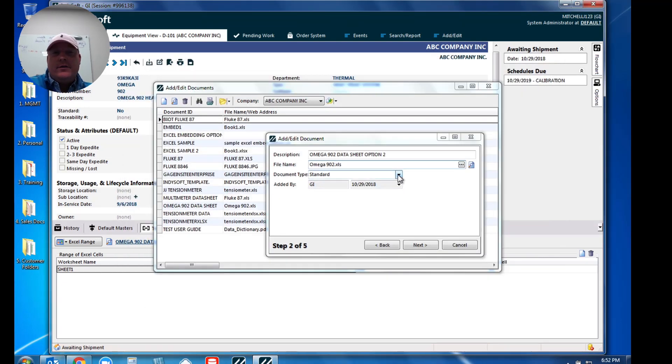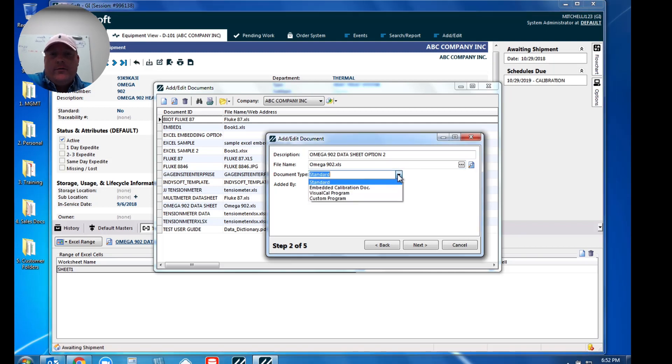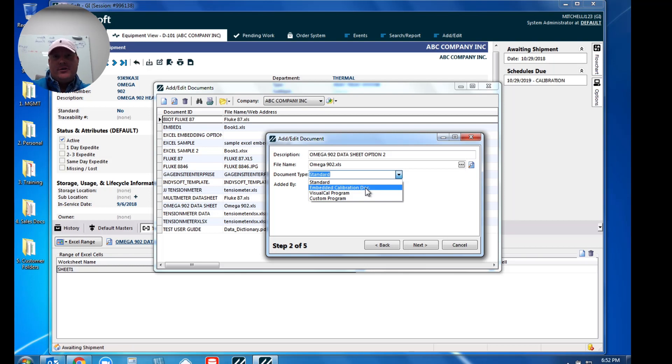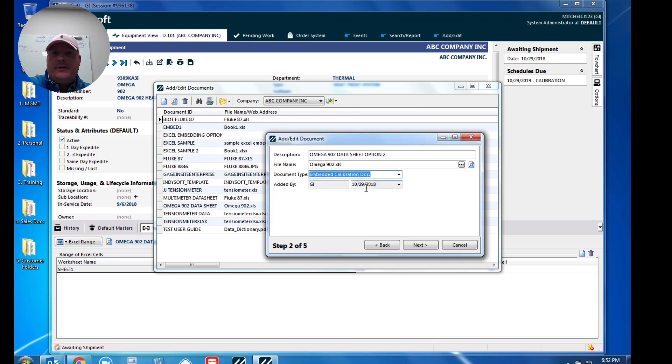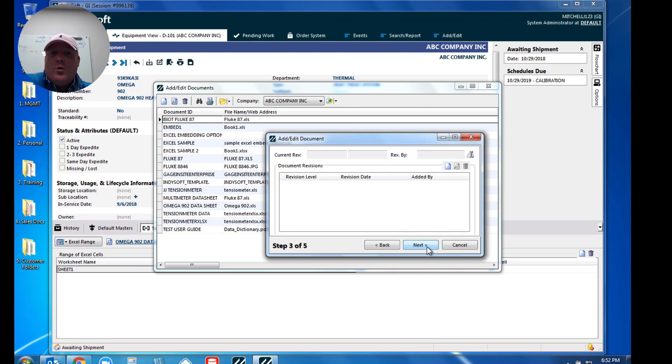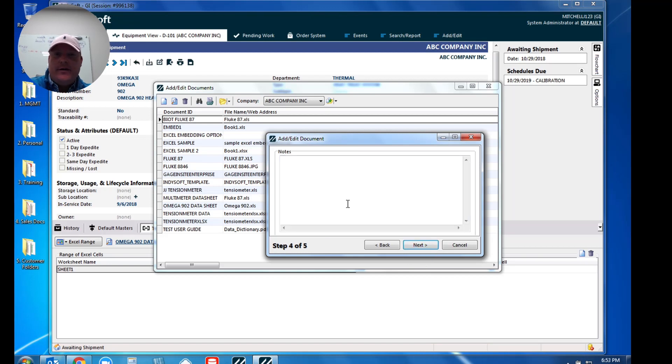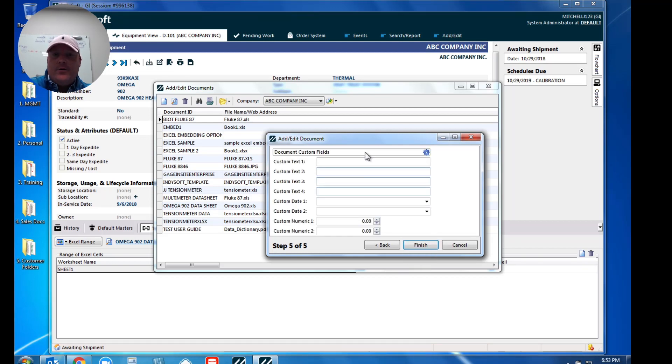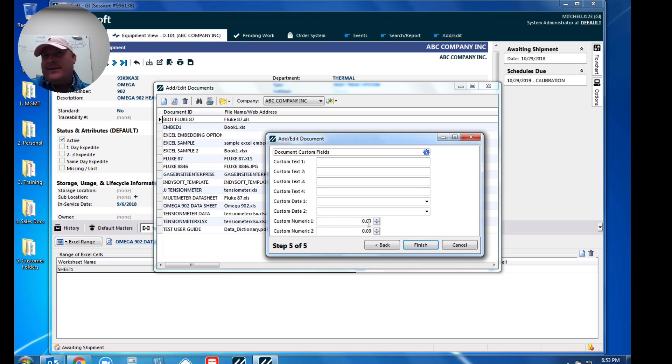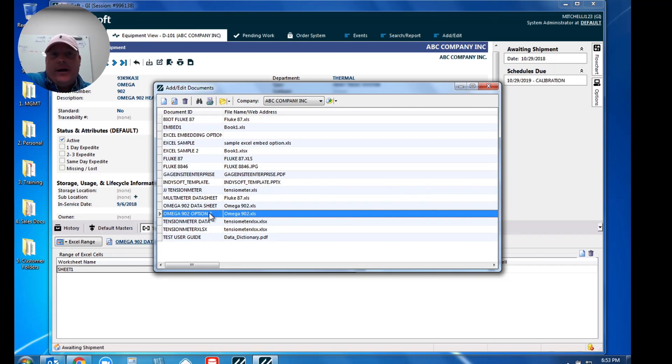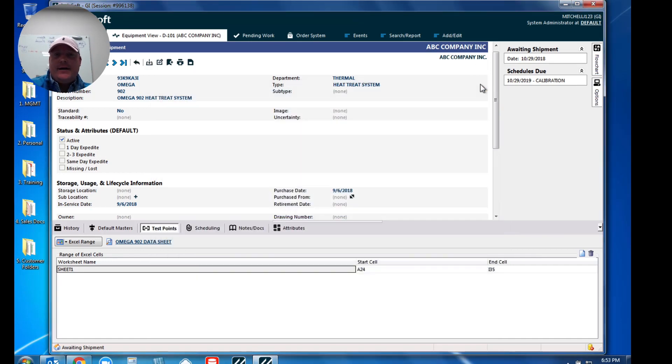Now here's the important piece. This is the important one for the document type. We must choose embedded calibration document, so that basically says out of all these documents, which ones are just data points and the ones that we specify as embedded cal doc are those. With any document you put in the database, there is revision control that you can utilize if necessary, along with notes, and then you even have the ability to utilize some of our bonus fields should you need those. So what I've done is I put Omega 902 option two into my system now.